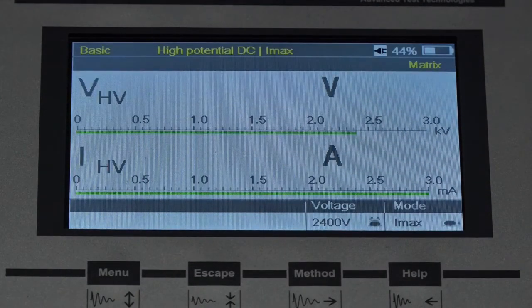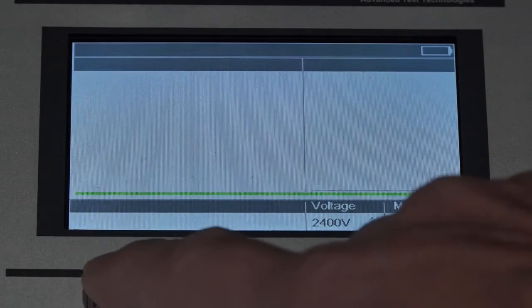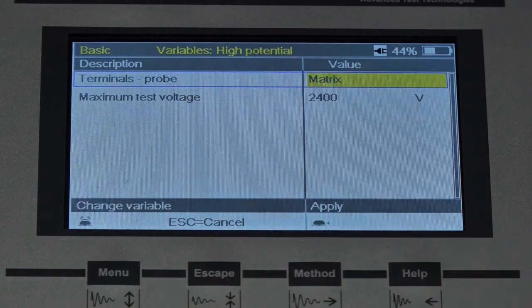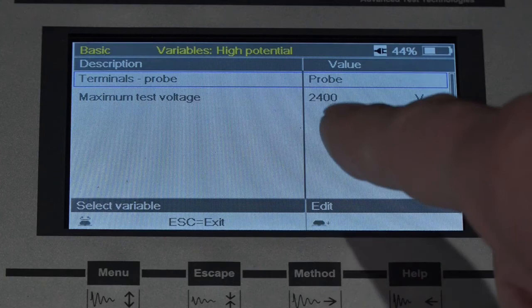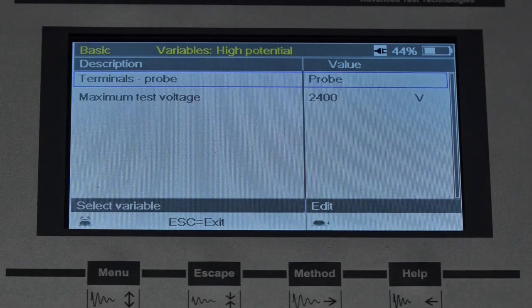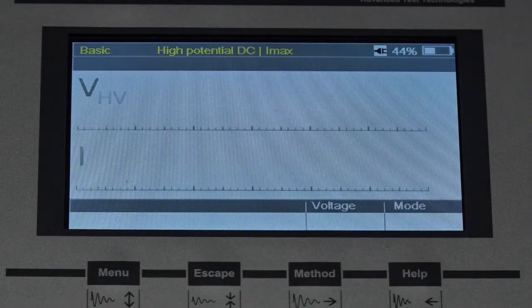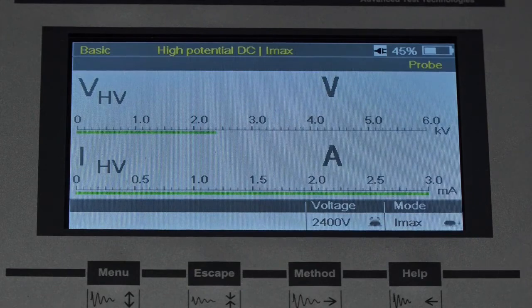Select it. Now you can see in the upper right hand corner it's saying that we're connected to the matrix at the moment. Let's change that. Let's press the menu button. Use the whiz wheel to select the terminals. Let's change it to probe. And now we have the separate high voltage test lead probe selected. Now you can also see here that the voltage has been already determined to 2400 volts. Let's save that. And let's start performing some testing.